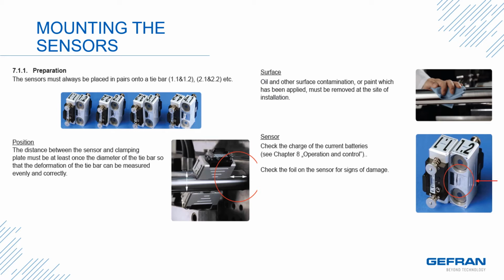Also, the tie bar surface where the sensor will be mounted must be wiped off to remove any oil, paint, or any surface contamination. You will also need to check to make sure the batteries are fully charged. The recommendation is to charge all the sensors the night before. Also check the foil on the bottom of the sensor to make sure there is no damage.